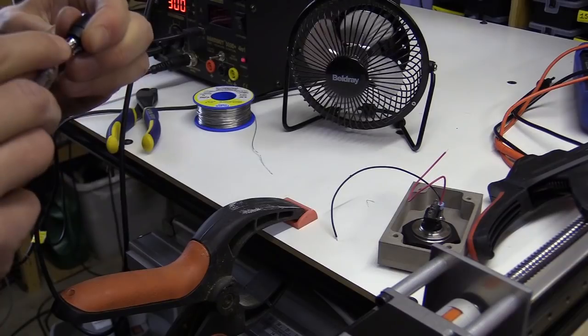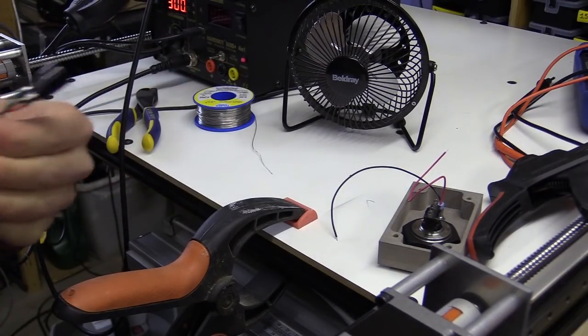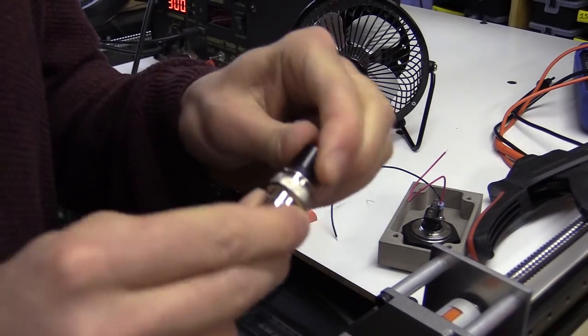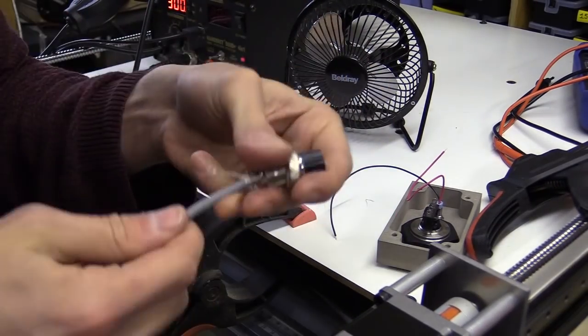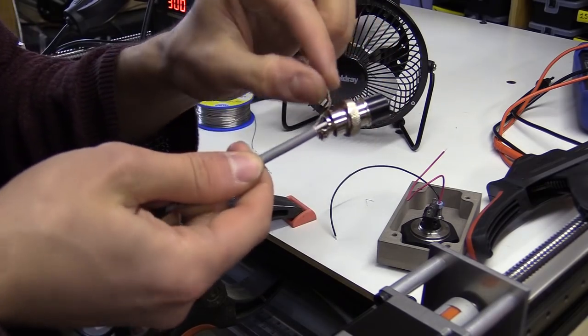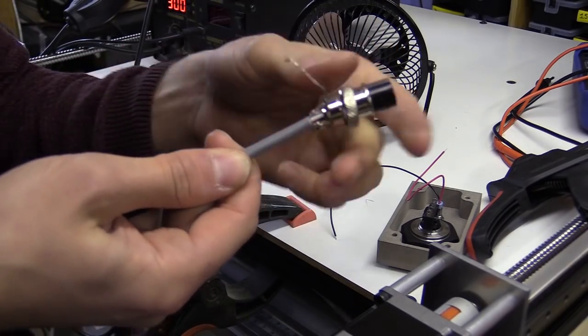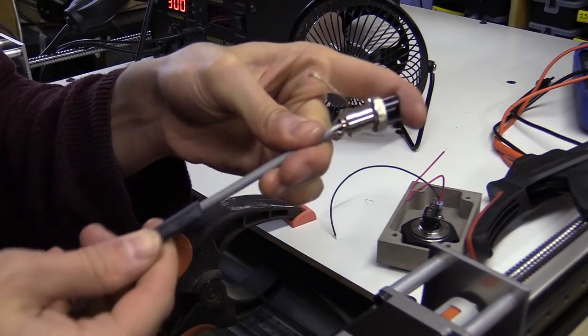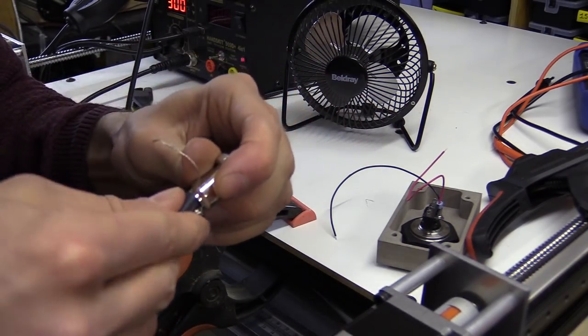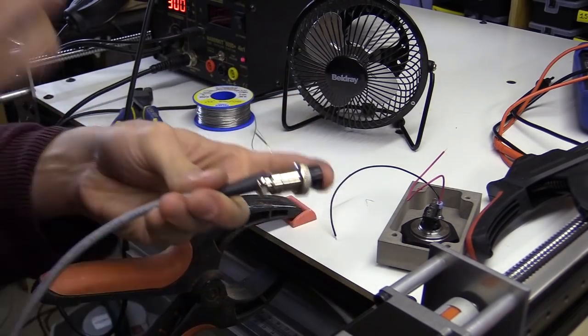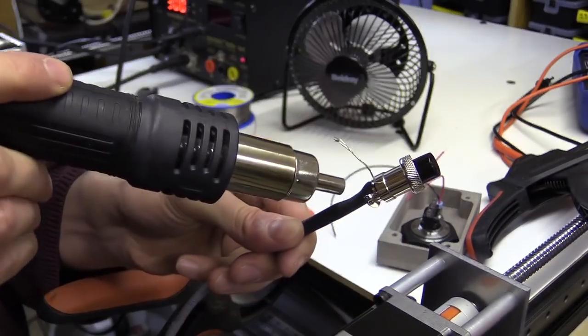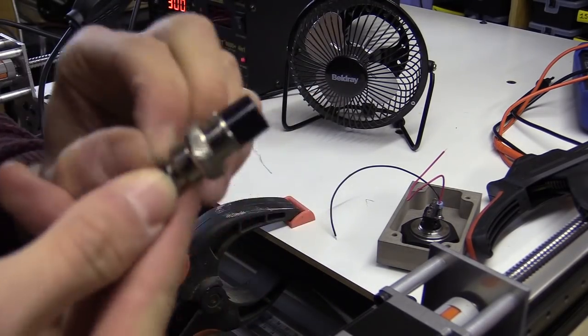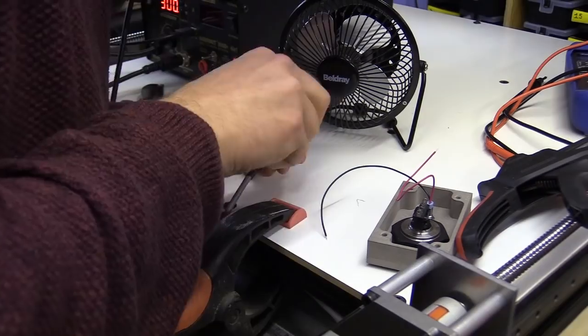So there's the end that's going to go onto the aviation panel mount. What I'm going to make sure I do is wrap this drain wire for EMI interference onto the outer casing of the socket. I'm going to wrap the drain wire in a figure of 8 around the cable clamp screws. This will connect the shielding to the wiring inside the enclosure which I can later terminate at a star earthing block. This will help protect against EMI interference.